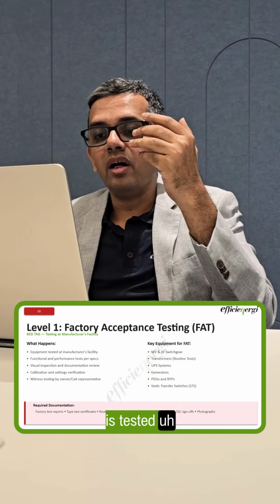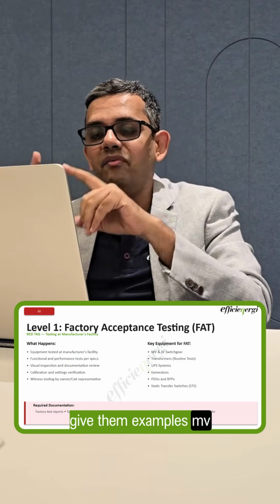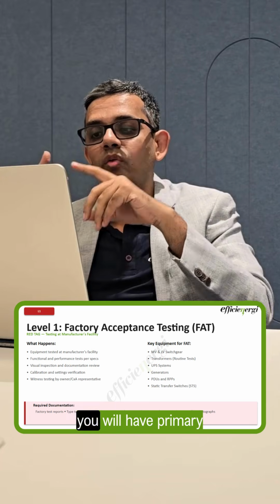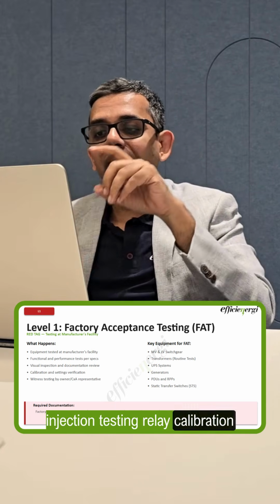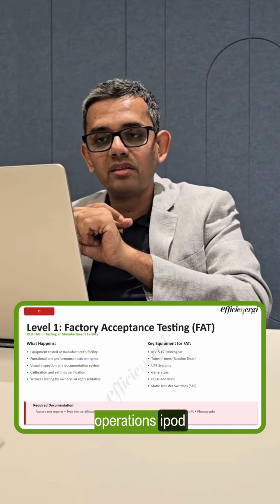What is tested? I'll give some examples. For MV switchgear, you will have primary injection testing, relay calibration and settings, interlock operations, hi-pot testing, and so on.